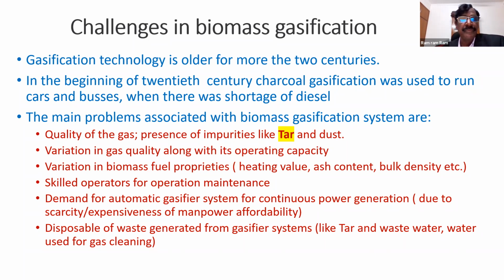That's why some people call it the turn down ratio. If we design a gasifier for 100 kilowatt, we should not go below 30% or so, to maintain a certain gas quality. So a 100 kilowatt system should not go below 30. At least we maintain the temperature at the minimum possible. Also, the engine efficiency is affected a lot when we operate at low capacity load, so it's better to operate at the higher. There is a variation in the gas quality depending on the operating condition. That is one of the biggest challenges. Generally, above 80% operation is very good for the gasifier as well as for the engine. It also needs skilled operators for operation and maintenance. And now work is going on for automation or semi-automation.